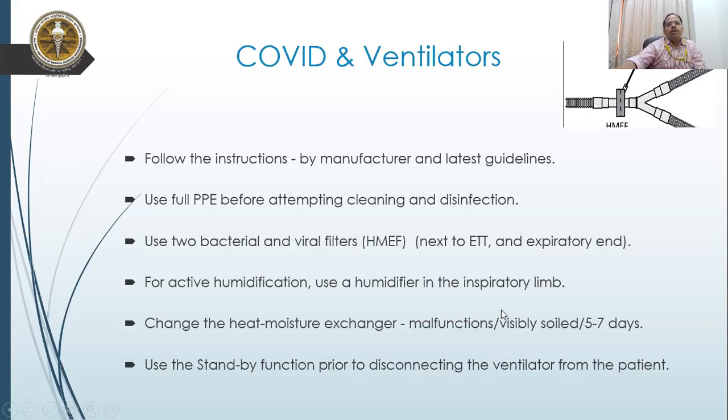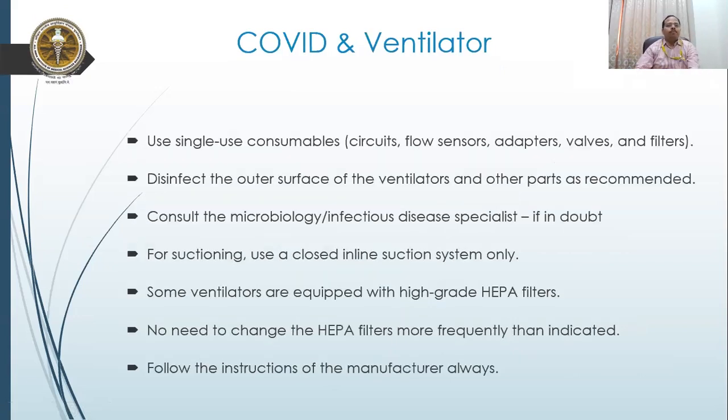Remember one thing, if you are going to change any filter or disconnect the circuit, always put the ventilator on the standby button, then clamp the endotracheal tube or take the patient on an ambu bag. If the patient is not tolerating much, then you disconnect or throw the filters, put a new one and then reconnect. The point here is the standby function of the ventilator has to be used if you are changing filters.